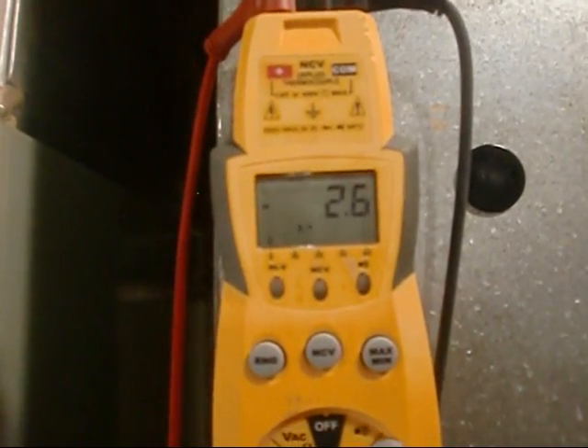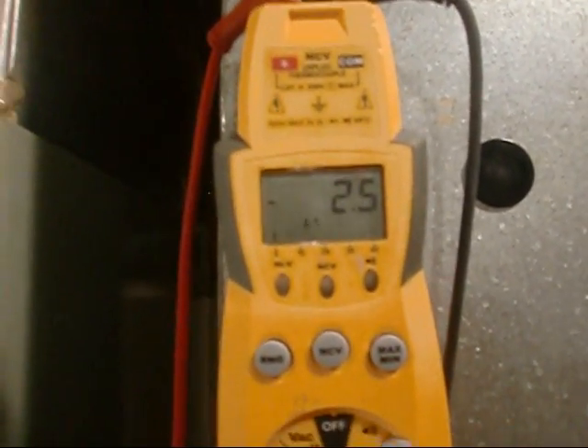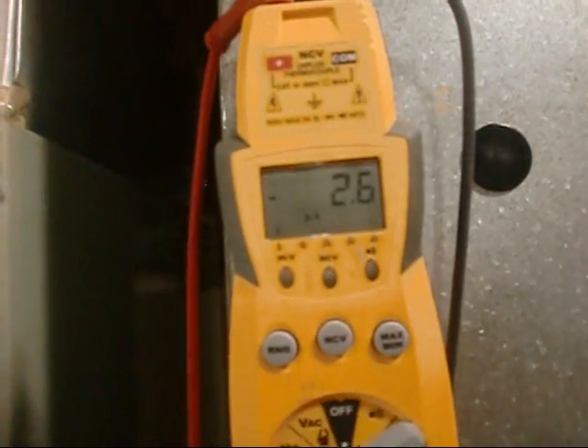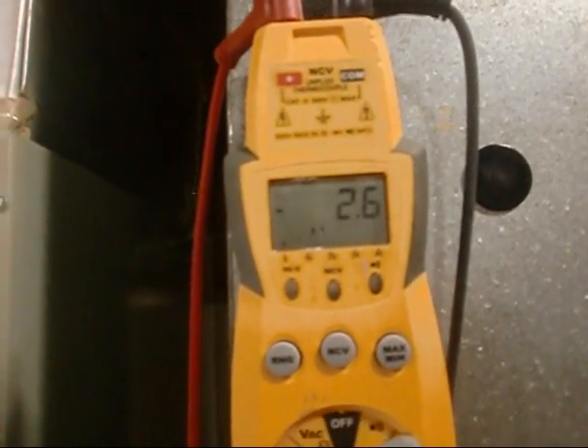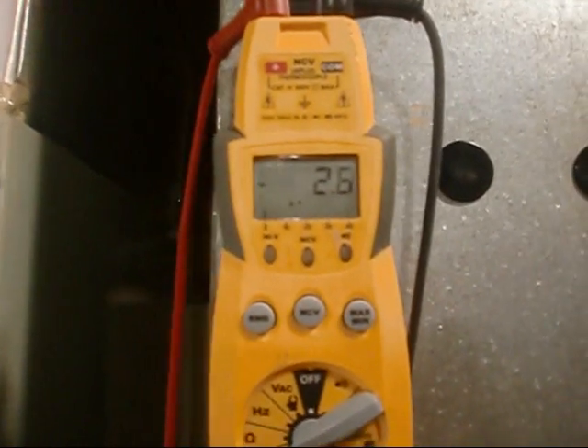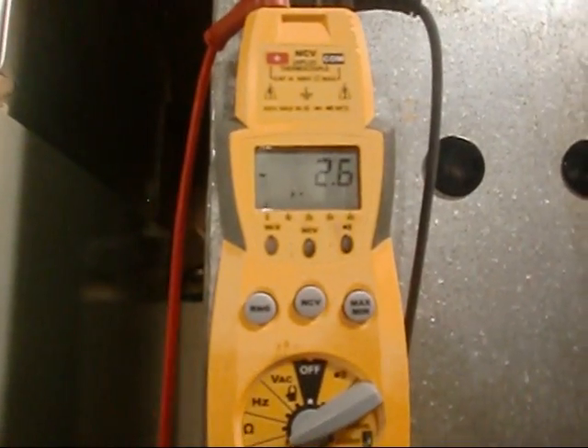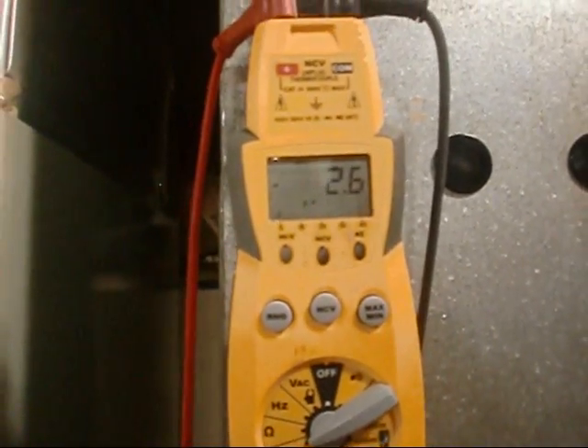All right brother, that's good, that indicates well, let's see if you're right. Anything above 2.5 is fine. I've actually seen them at 2.0, but that's probably needing a good cleaning. Anything below 2.5 needs a cleaning, and anything below 2.0 needs to be replaced.